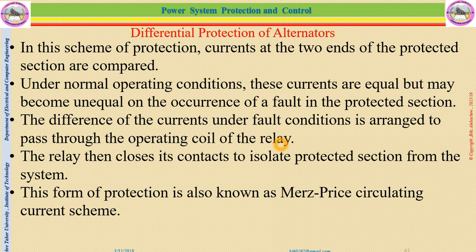So under normal conditions, those currents are equal, but may become unequal on the occurrence of a fault in the protected side. That fault may be a line to ground fault, a line to line fault, or other types of fault. By any means, if the fault is present, these currents cannot be equal. So the difference of the current under fault condition is arranged to pass through the operating coil of the relay. The relay then closes its contact to isolate the protected alternator from the system.